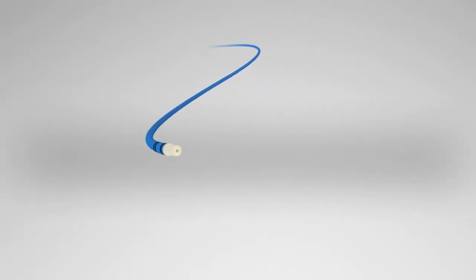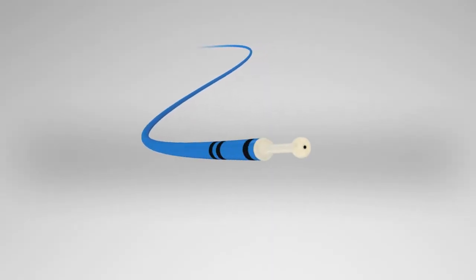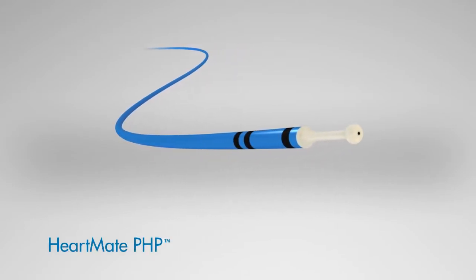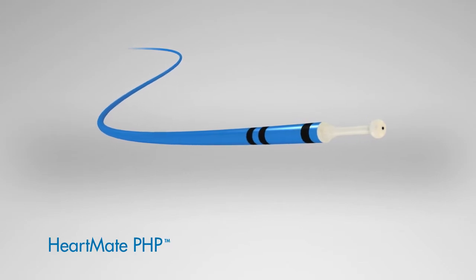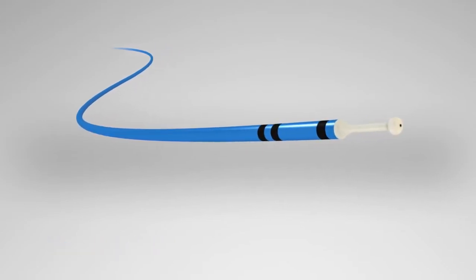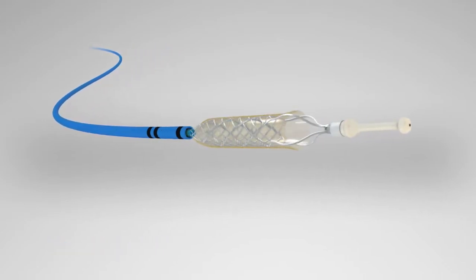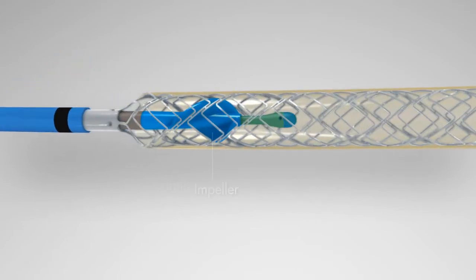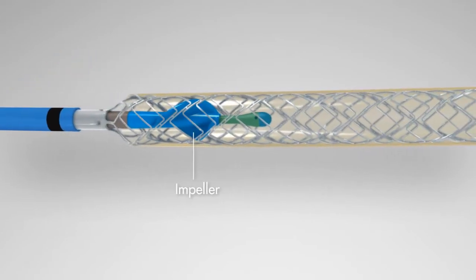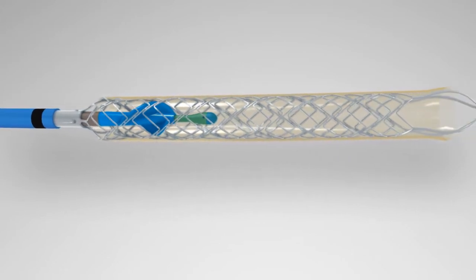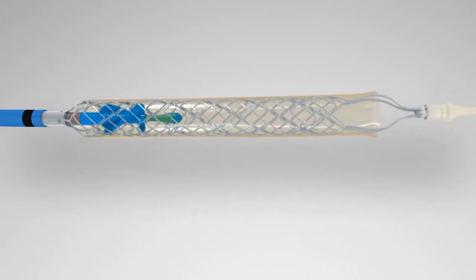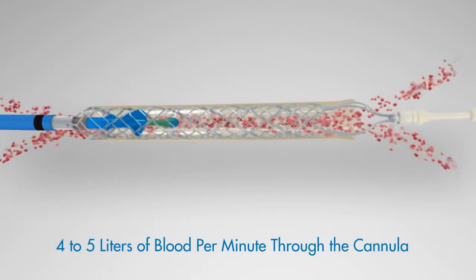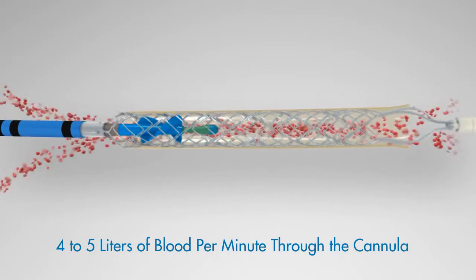HeartMate PHP from Thoratec Corporation is a low-profile percutaneous heart pump designed to provide rapid left ventricular hemodynamic support. The key feature of the PHP is its expandable covered nitinol cannula with integrated impeller. The cannula is positioned across the aortic valve and the impeller spins to move 4 to 5 liters of blood per minute through the cannula from the left ventricle into the ascending aorta.